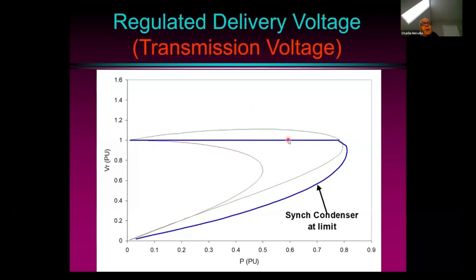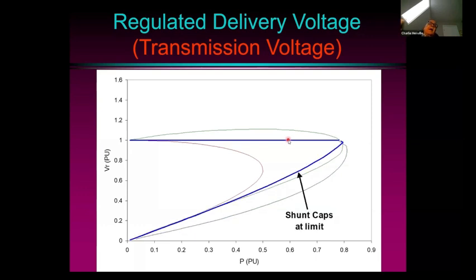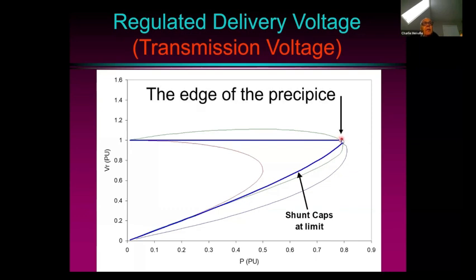But what happens when you reach the limits of your capability, then the amount of power you can deliver drops off very quickly. In this case, the reactive power is being delivered by a synchronous condenser, but that is more expensive and complicated than just the addition of shunt capacitors. So it's a natural inclination to try and just add more shunt capacitors, but then you get a PV curve that looks something like this, and we say that this is the edge of the precipice.